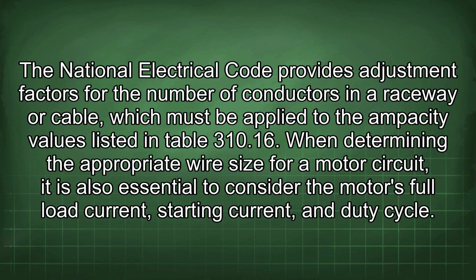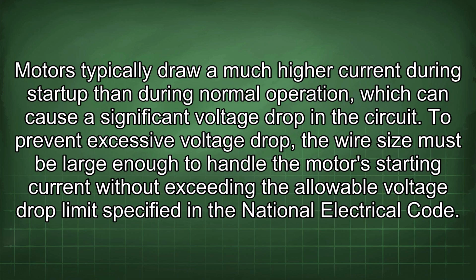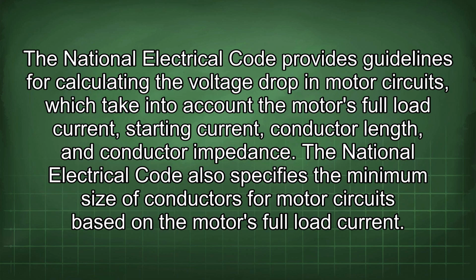When determining the appropriate wire size for a motor circuit, it is also essential to consider the motor's full load current, starting current, and duty cycle. Motors typically draw a much higher current during startup than during normal operation, which can cause a significant voltage drop in the circuit. To prevent excessive voltage drop, the wire size must be large enough to handle the motor's starting current without exceeding the allowable voltage drop limit specified in the National Electrical Code. The National Electrical Code provides guidelines for calculating the voltage drop in motor circuits, which take into account the motor's full load current, starting current, conductor length, and conductor impedance.